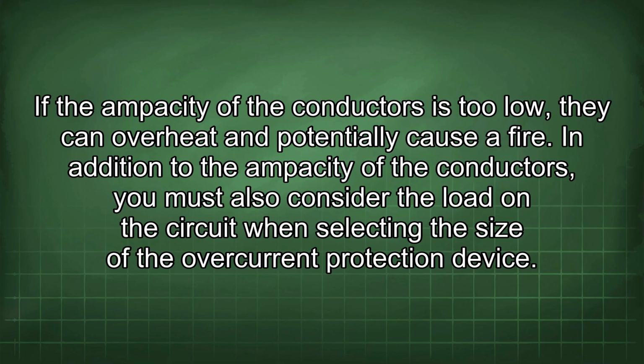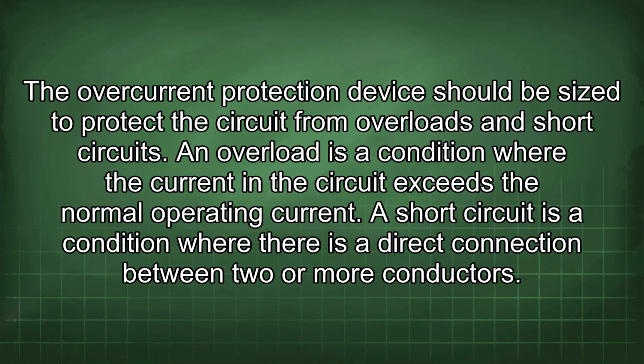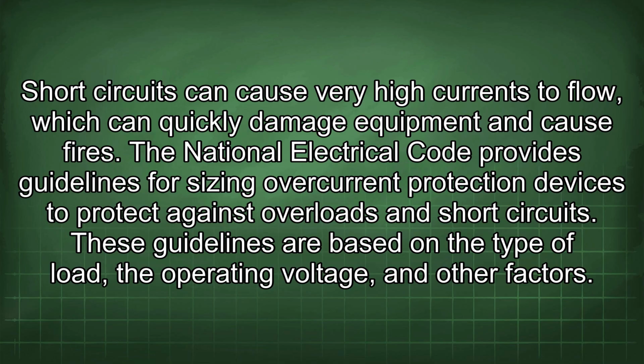In addition to the ampacity of the conductors, you must also consider the load on the circuit when selecting the size of the overcurrent protection device. The overcurrent protection device should be sized to protect the circuit from overloads and short circuits. An overload is a condition where the current in the circuit exceeds the normal operating current. A short circuit is a condition where there is a direct connection between two or more conductors. Short circuits can cause very high currents to flow, which can quickly damage equipment and cause fires.